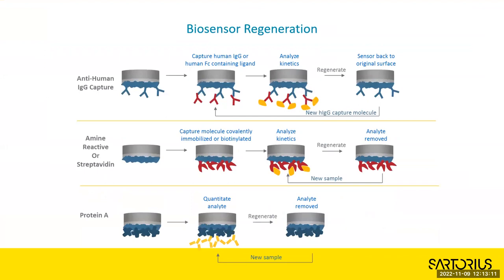One of the most common questions is whether biosensors can be used more than once. The answer is it depends. Some biosensors can be regenerated multiple times. With protein A, for instance, you bind the Fc region of antibodies to the sensor. If you dip it into acid, it strips away all the antibodies, leaving a blank sensor. You can reuse it up to 10 times, so you can do a whole 96-well plate with just eight sensors.